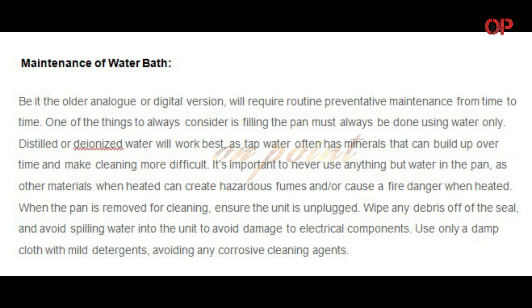Maintenance of Water Bath: Whether it is the older analog or digital version, routine preventative maintenance is required from time to time. Always fill the pan using water only — distilled or deionized water works best, as tap water often has minerals that can build up over time and make cleaning more difficult. Never use anything but water in the pan, as other materials when heated can create hazardous fumes or cause a fire danger. When the pan is removed for cleaning, ensure the unit is unplugged. Wipe any debris off the seal and avoid spilling water into the unit to avoid damage to electrical components. Use only a damp cloth with mild detergents, avoiding any corrosive cleaning agents.